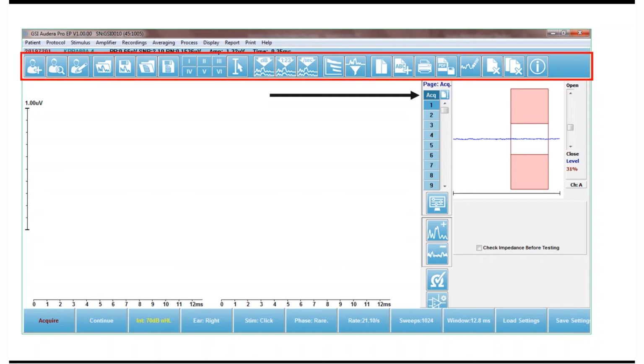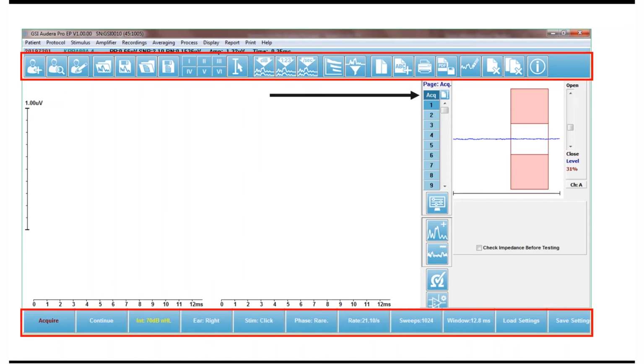There is a top toolbar that includes a variety of icons that you will use during collecting, such as selecting a waveform marker, maybe adding some cursors, sorting your data, etc. Then you have the collection toolbar, which is at the bottom of the screen. And this toolbar has common test settings that you are most likely going to change during a test. So intensity, the test ear, the stimulus, phase, rare, con, both, the rate, sweeps, etc. So those are common settings that you'll change. You also have the side toolbar, and that includes icons for measuring impedance and checking your amplifier settings.